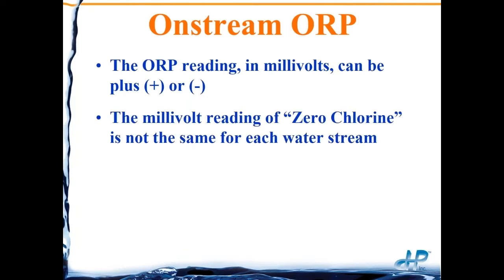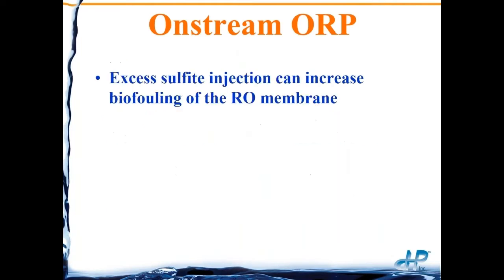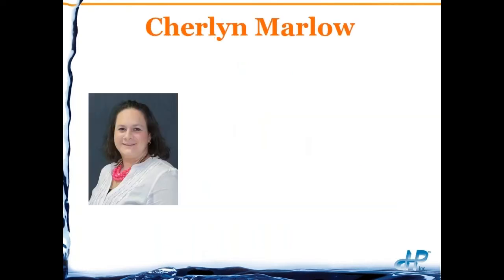As Cherlyn will go over, we're talking about millivolts plus or minus. It can be a challenge with different waters to find exactly where zero chlorine is. Most of the time we like to overfeed sulfite to be absolutely sure we don't have any oxidation of the membrane, but excess sulfite can also cause biofouling issues. So we want zero chlorine and just a small excess — maybe half to one part per million of excess sulfite. It takes a little trial and error to find the right millivolt reading at your plant.